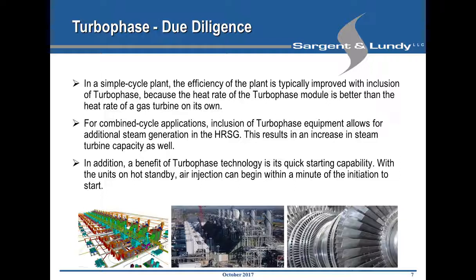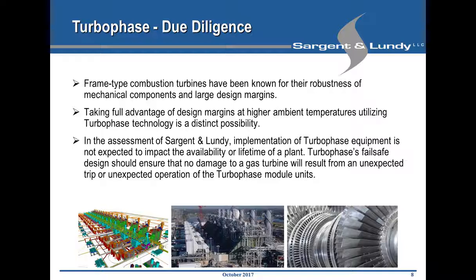Last but not least, many of the owners and operators of gas turbine power plants in simple or combined cycle require quick startup and quick ramp up capability. With Turbophase technology on hot standby, air injection can begin very quickly, and thus the power station overall can follow the ramp rate of the gas turbine very quickly and provide additional power output.